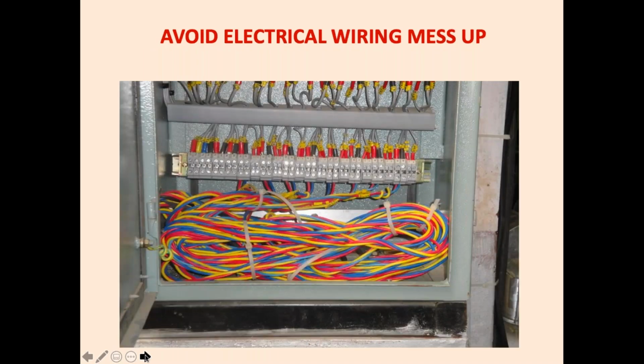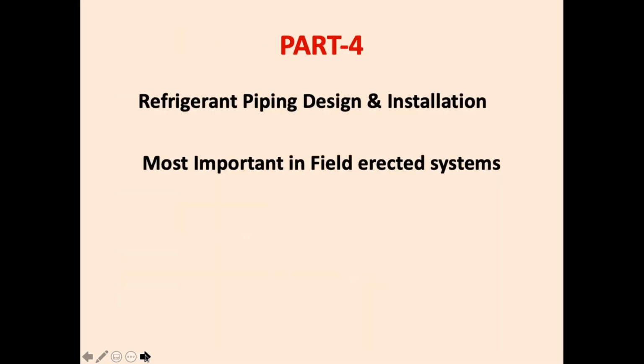Extra wiring, lot of extra wiring if you are having, just remove it. Don't keep bundles of wiring inside your panel, below the panel. You won't be able to trace out your wires. So very, very important, provide just adequate wiring for the panels. We go to the next very, very important part, which is piping and installation. Most important part in a field erected system.